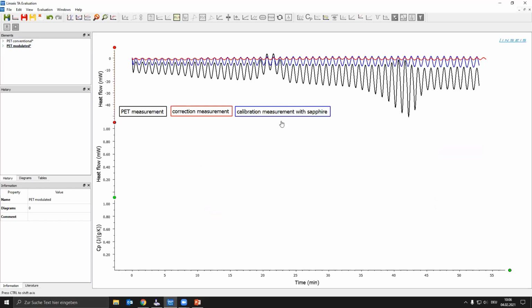Now let's go for the modulated DSC measurement. Here I've plotted in the upper part of this diagram all the curves we need. The red one is the correction curve, the blue one is the calibration curve, and the black one is my sample measurement. And just a hint, if you use just the crucible without any sample inside for the correction measurement, the amplitude will be pretty small due to the low heat capacity. With your sapphire inside, the amplitudes of your result, so the DSC measurement itself, get higher.